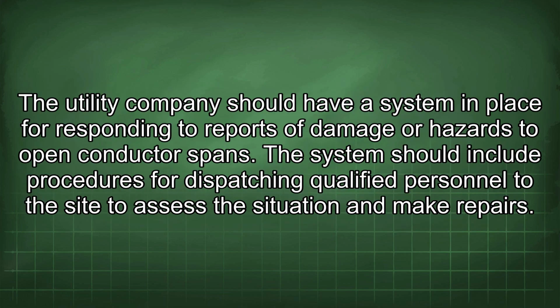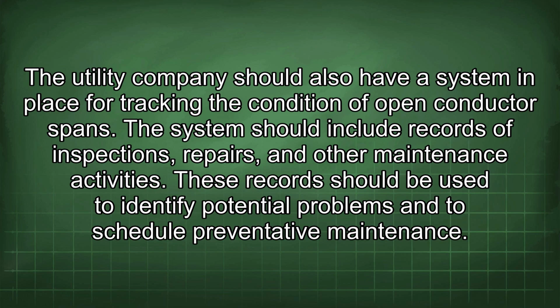The utility company should have a system in place for responding to reports of damage or hazards to open conductor spans. The system should include procedures for dispatching qualified personnel to the site to assess the situation and make repairs. The utility company should also have a system in place for tracking the condition of open conductor spans. The system should include records of inspections, repairs, and other maintenance activities. These records should be used to identify potential problems and to schedule preventative maintenance.